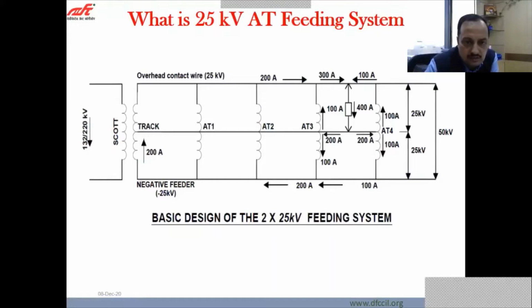On the secondary side we have, as I showed, the overhead contact wire at 25 kV and this negative feeder at minus 25 kV. So these are the two feeders at plus 25 and minus 25 kV. These run along the complete corridor. That is why the system is known as the 2 into 25 kV system, because there are two conductors running at 25 kV, plus and minus. In this system we make use of these auto transformers, AT1, AT2, AT3 and so on.